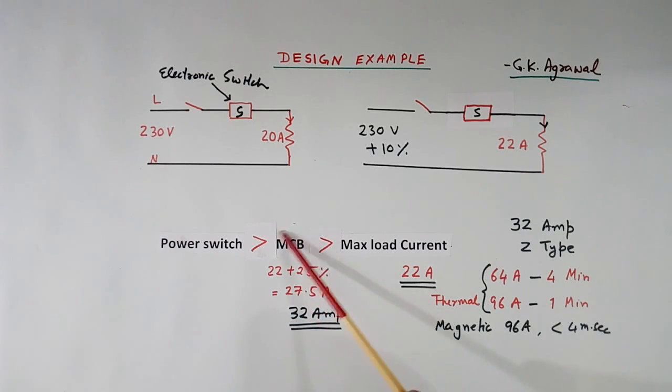So power switch should take more than 32 A continuously. Again for protection, this MCB will operate like this. If it's due to thermal protection, for 64 A current it will take 4 minutes. If it is Z-type, for 96 A it will trip in 1 minute. And magnetic protection will operate in less than 4 ms if current flows 96 A. So this switch should be rated sufficiently such that it can take continuously 32 A, more than that. According to me, if this is 32 A, it should be at least 40 A.